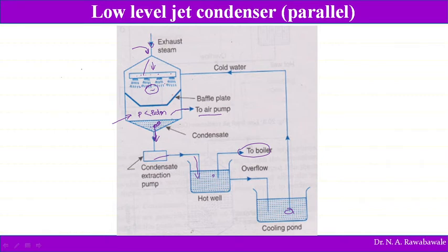So the question here is why the condensate extraction pump is required. As I told you, when steam enters this condenser, it occupies very small space and large space remains vacant, and that is nothing but vacuum being created. Vacuum means pressure is below atmospheric pressure. Because of the low pressure, the flow of fluid always takes place from high pressure to low pressure. So it is necessary for us to remove this condensate from this condenser.